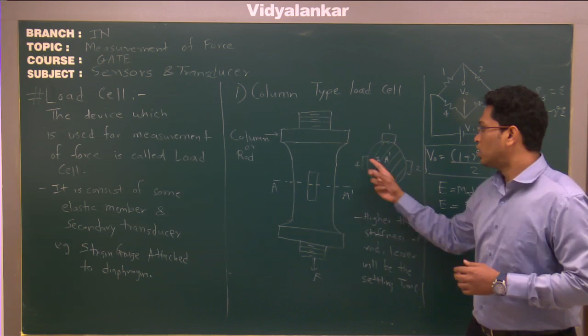So the load cell is a device which consists of some primary transducer and some secondary transducer. Usually some elastic member is considered as a primary transducer and another kind of arrangement is used as a secondary transducer. Now the first type of load cell is the column type load cell. In a column type load cell, you have a metal column or a rod. On this rod we have strain gauges attached.